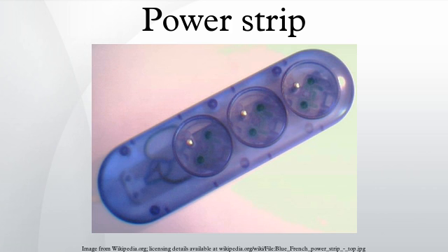Any plug fitted to the socket outlet unit must comply with the requirements of BS 1363-1, specification for rewirable and non-rewirable 13A fused plugs. Plugs must also be independently approved and marked in accordance with the requirements of the regulation. If a socket outlet unit contains additional control circuits or surge protection circuits, they will fall within the scope of the Low Voltage Directive 2006/95/EC and must be CE marked. Socket outlet units with control circuits also fall within the scope of the EMC Directive 2004/108/EC.